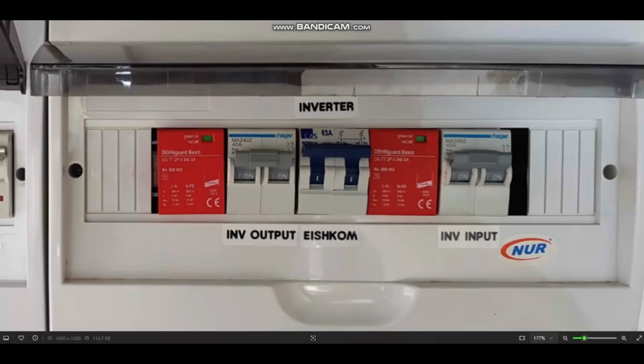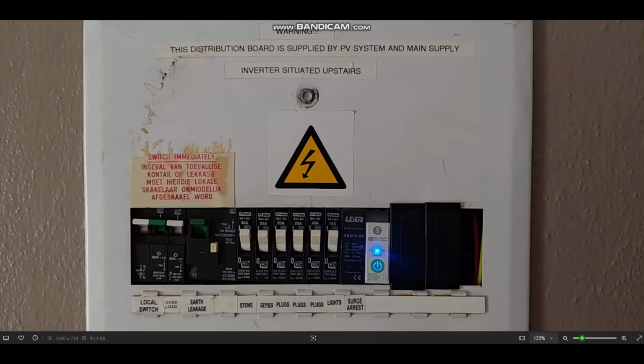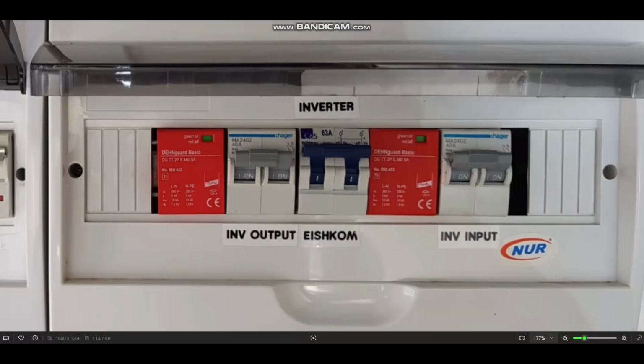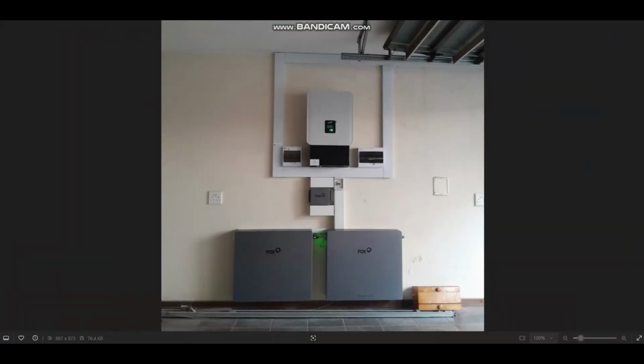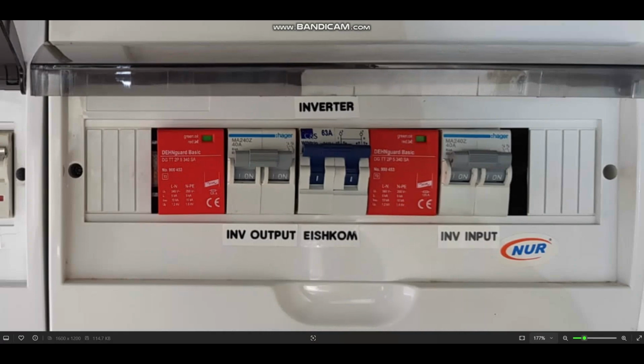Why do we have that? Well, simply put, if one of the appliances on your main distribution board malfunctions, there's a good possibility it could send out bad power. That is power with a high voltage or frequency spike. And this little surge protector will protect your 150,000 Rand, 250,000 Rand, 500,000 Rand solar investment from that voltage spike.